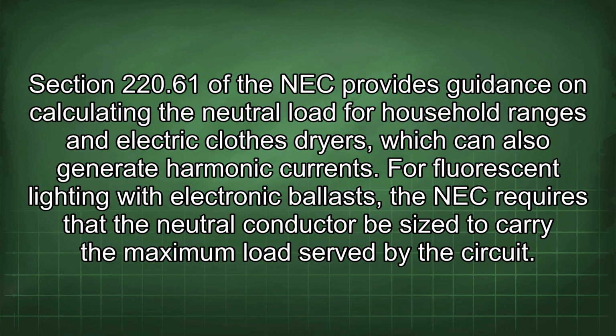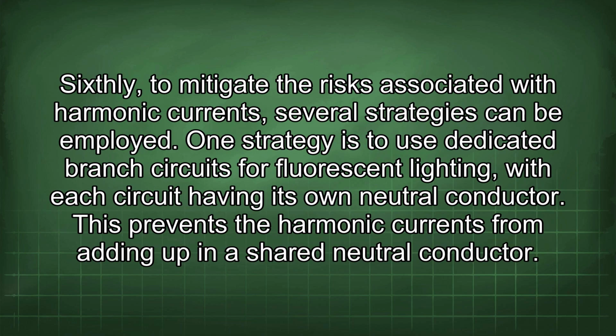For fluorescent lighting with electronic ballasts, the NEC requires that the neutral conductor be sized to carry the maximum load served by the circuit. Sixthly, to mitigate the risks associated with harmonic currents, several strategies can be employed.